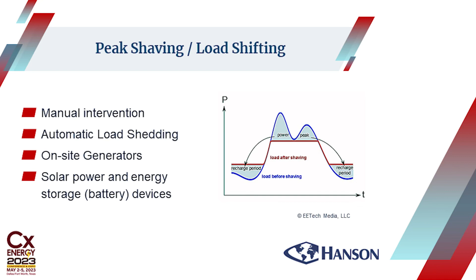Okay, so some of the other things out there that engineers or consultants need to consider are peak shaving and load shifting, and whether it's done manually, with a manual intervention to start shedding loads, or whether there's some automatic shedding if you start to get close to your peak. These are the things that are out there. You have a lot of clients potentially in mission critical areas, like a hospital or data center, where they have a bank of generators, and they've got the capability of idling at least a portion of their load and bringing the generators on to control their peak, and that's what's critical. But now what's happening is you also have distributed generation areas where people have perhaps solar PV, and they've installed batteries, okay?